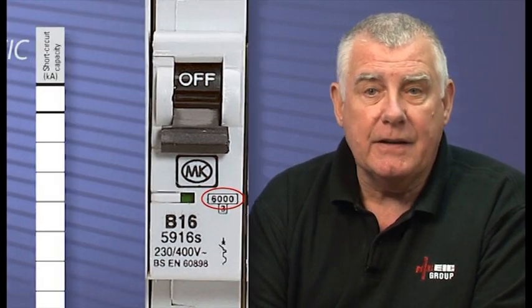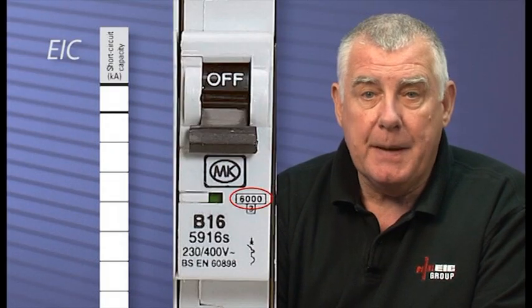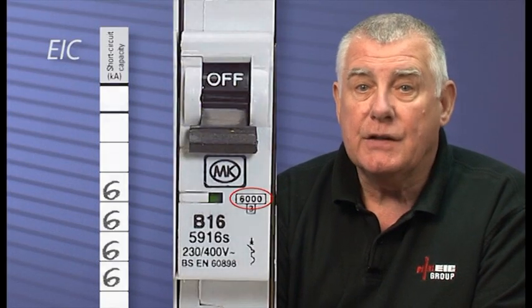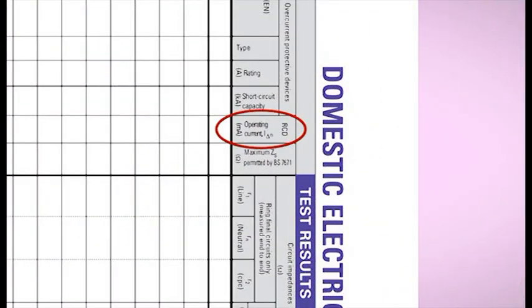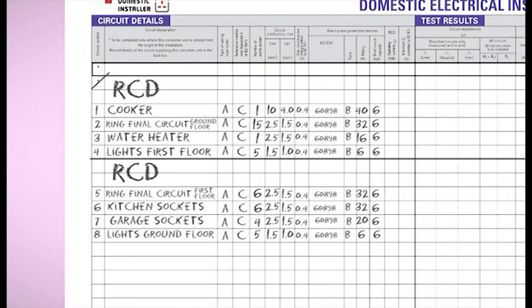And for a BS EN circuit breaker it is displayed in a rectangular box. As the heading of the column is kA, it may be necessary to convert from amps to kiloamps. The following column is for the operating current of any RCD protecting the circuit. Don't forget this includes RCBOs. For our circuit detail sheet we saw earlier, it will only be necessary to fill in the RCD details in the rows set aside for the two RCDs. And then you can put a ditto in the rows underneath for each circuit.